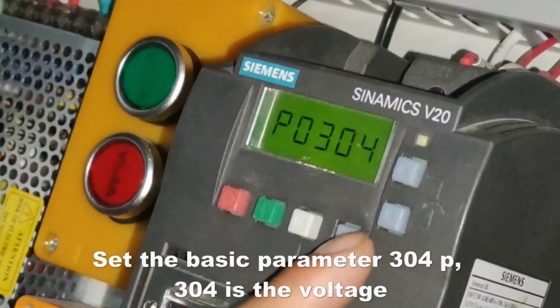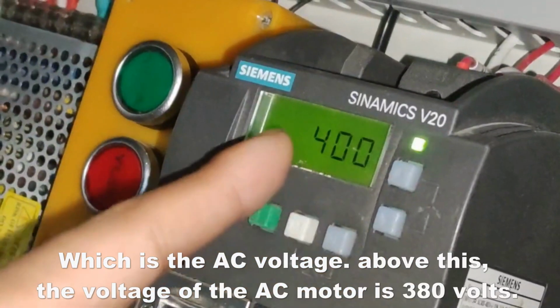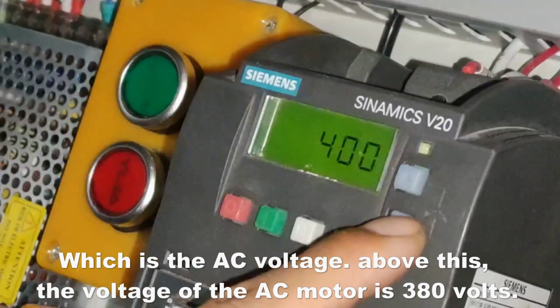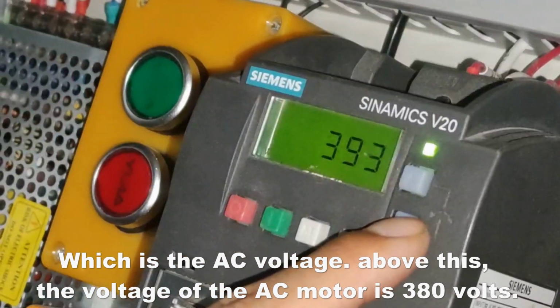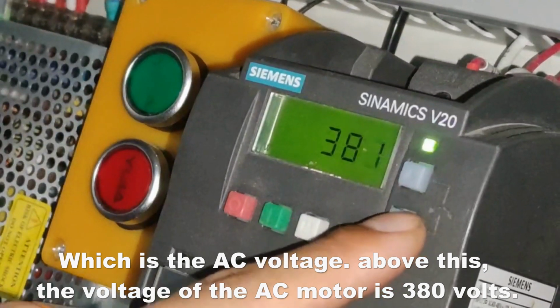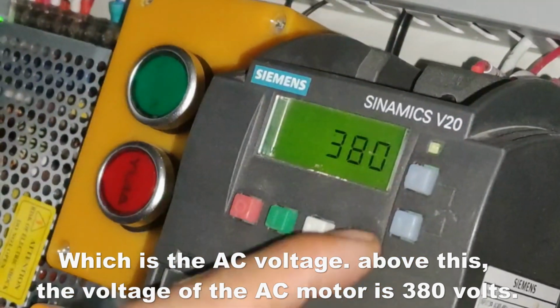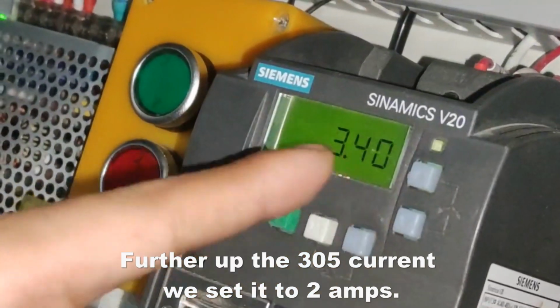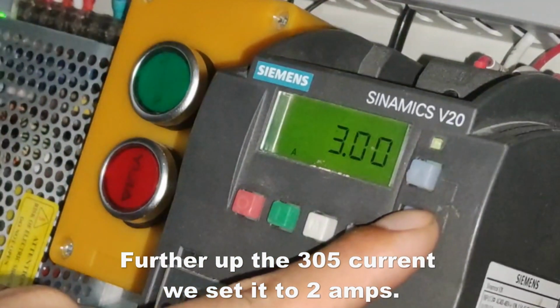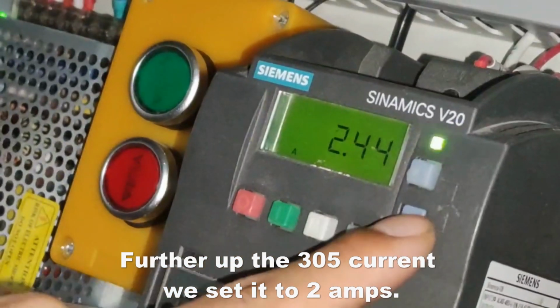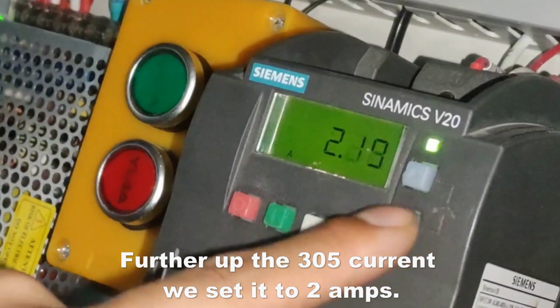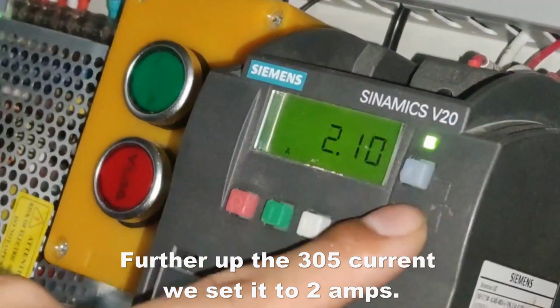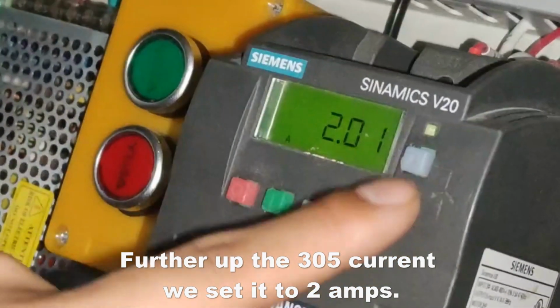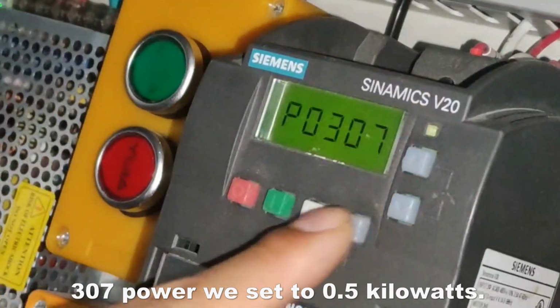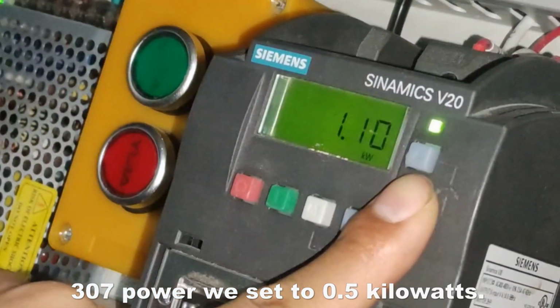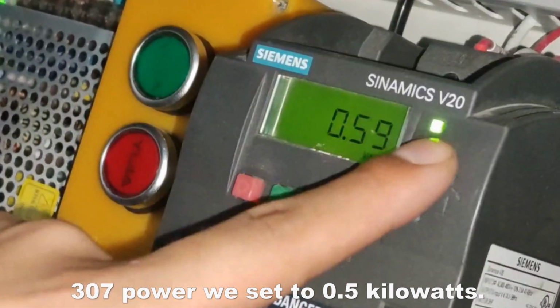P304. 304 is the voltage, which is the AC voltage. Above this, the voltage of the AC motor is 380 volts. Further up, the P305 current, we set it to 2 amps. P307 power, we set to 0.5 kilowatts.